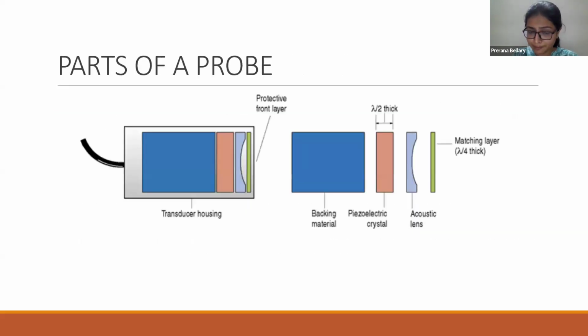Coming to parts of a probe, it has 7 major parts. We have the housing case, the electrical shielding, and the acoustic insulation. What is most important to know is that there is a piezoelectric crystal, which has a backing material at the back, an acoustic lens in the front, and a matching layer between the crystal and the lens. The piezoelectric crystal produces ultrasound waves. The acoustic lens focuses this beam. The matching layer decreases the impedance, and so it improves the transmission of the ultrasound waves.